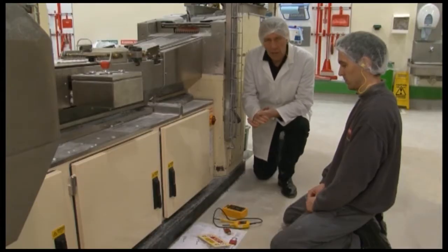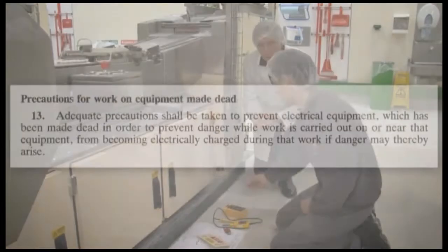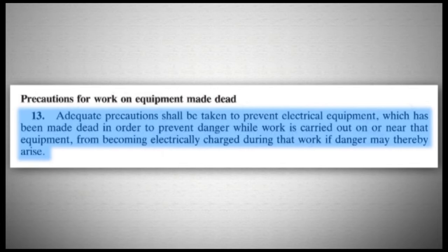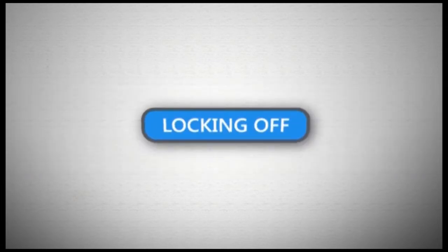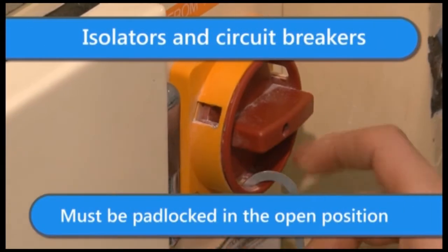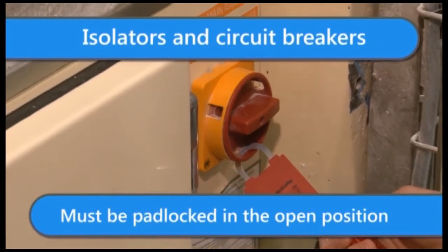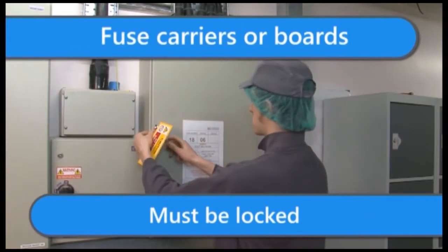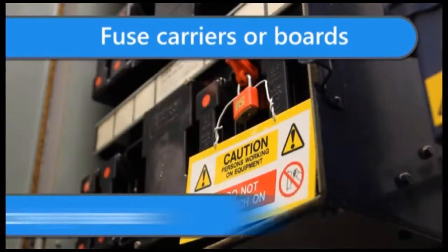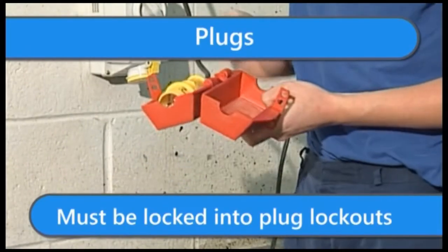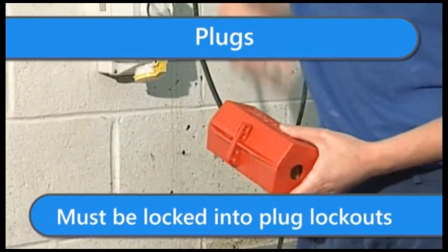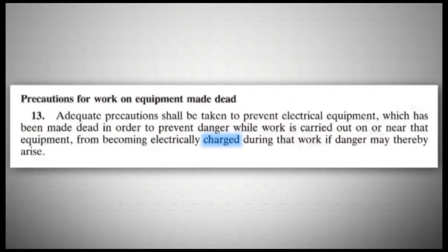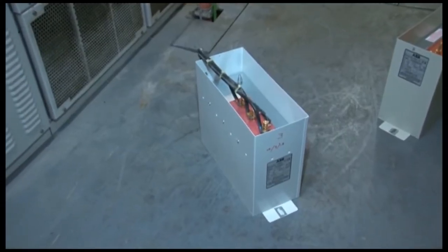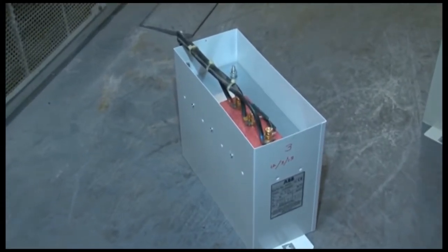This is not sufficient, however, since Regulation 13 requires that precautions are taken to prevent the equipment becoming charged while work is in progress, and this is achieved by locking off. For example, the isolator or circuit breakers must be padlocked in the open position. Fuse carriers or fuse boards must be locked, and the fuses securely retained. All plugs must be locked into plug lockouts. Notice that the word charged is used, not live. So the presence of stored or induced electrical energy also has to be considered.